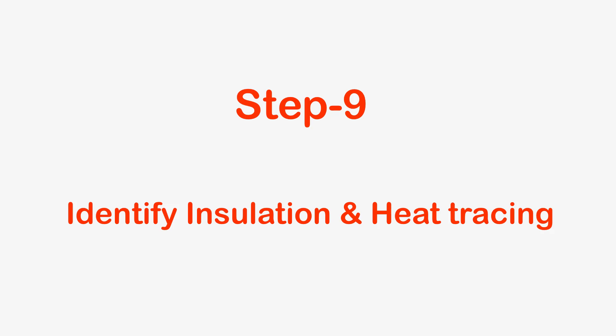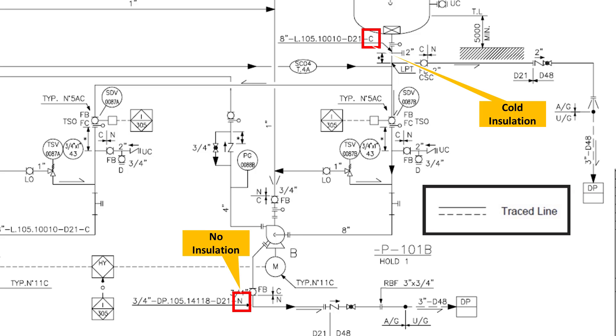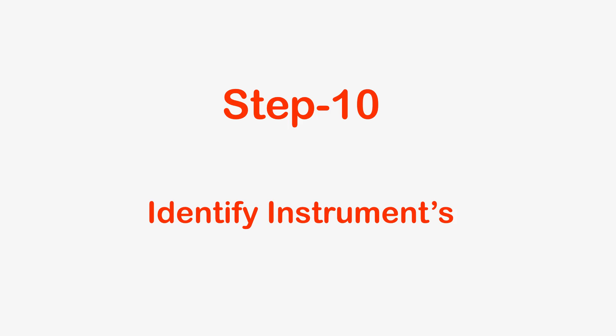Step 9: Identify Insulation and Heat Tracing Details. Here we should identify whether the line is insulated or not. This information is generally given along with the line numbers, indicated by a letter: N for no insulation, C for cold insulation, H for hot insulation. To identify heat-traced lines, look for the line with double lines as shown in the diagram.